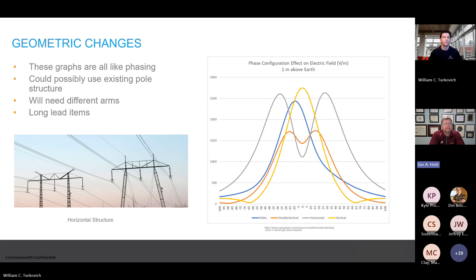You can see the difference: the yellow, which is the vertical structure with a single conductor on it, has a high peak, but very nice performance at the edge of right of way. As we go to that double vertical with cross phasing, we get that real nice cancellation in the middle, which is very nice for mitigating peak values. But you can also see that it pushes that electric and magnetic field out towards the edge of the right of way, in this case the electric field.